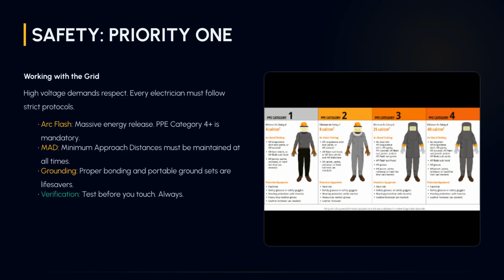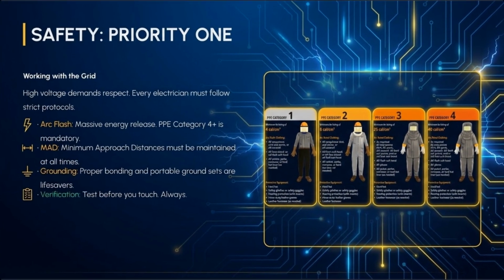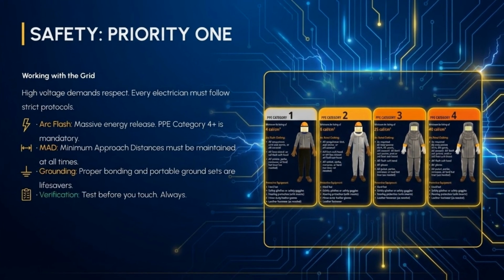Safety is paramount when working with high voltage. Be prepared for arc flash events with mandatory PPE Category 4+. Always maintain minimum approach distances, use proper grounding, and verify isolation by testing before you touch. This visual demonstrates the required personal protective equipment categories. Remember that high voltage requires strict adherence to safety protocols to prevent arc flash and maintain safe minimum approach distances.